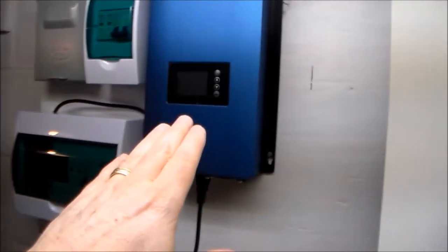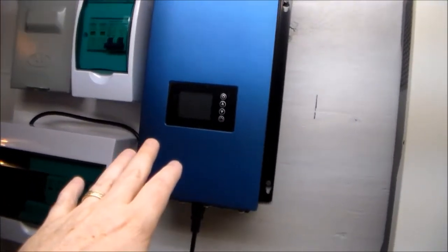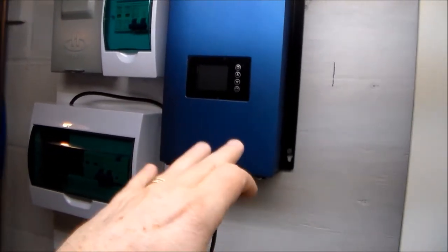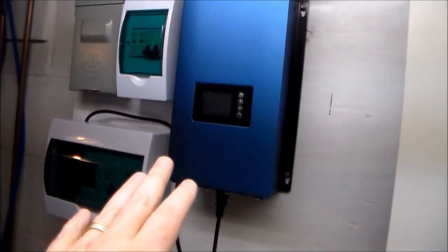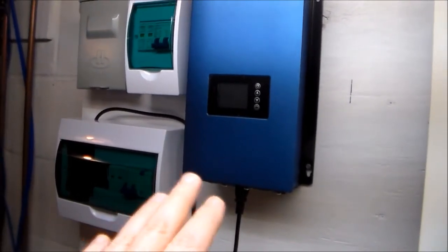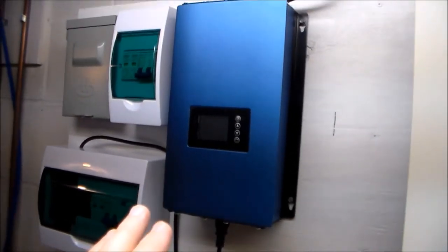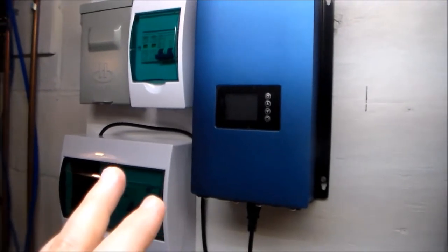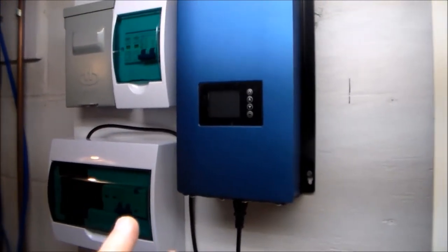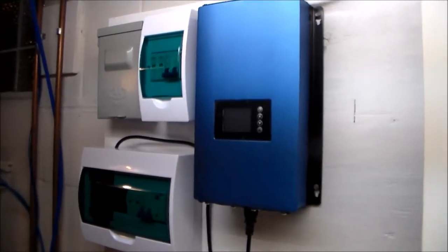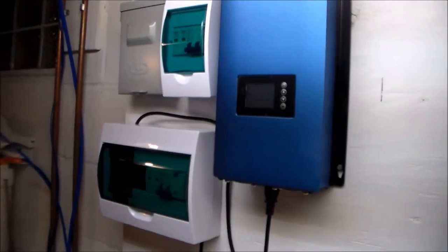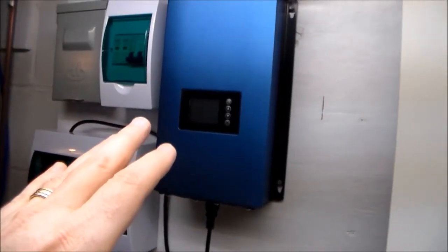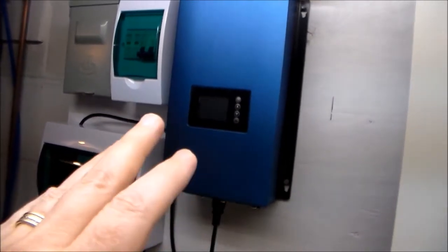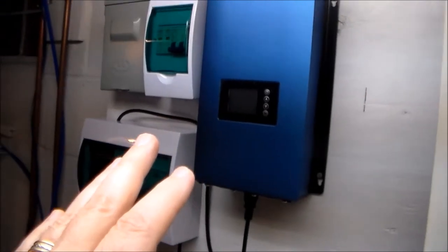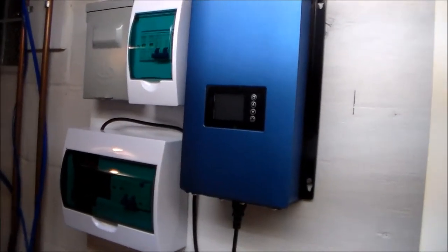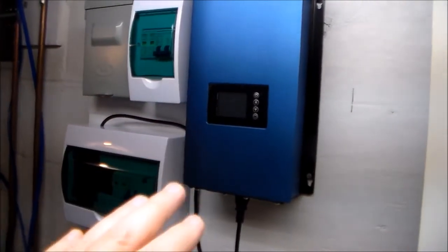So keeping that in mind, we want to now consider what this device is looking for. Now, there are a couple different versions of this Grid Tie Inverter on the market, and the particular one that I have is a 1 kilowatt or 1000 watt inverter, and it is expecting between 45 and 90 volts. Now, there are some that will start up at a much lower voltage, but this particular one is rated between 45 and 90 volts. So we're going to be looking at a minimum of 45 volts and a maximum of 90 volts coming from the solar panels, so that this operates the way that it is meant to operate.